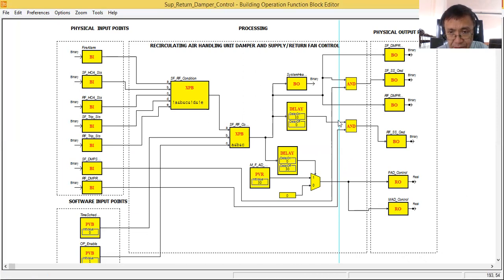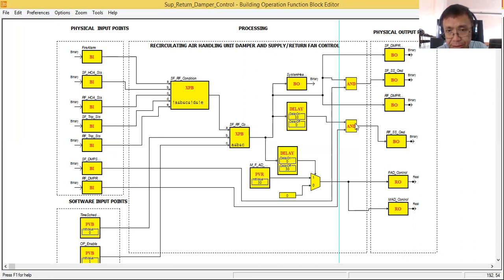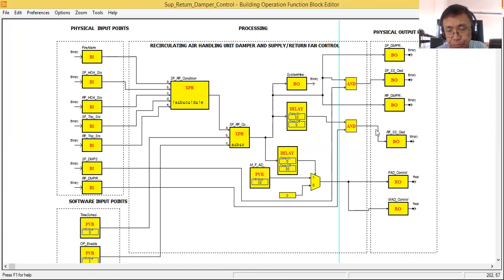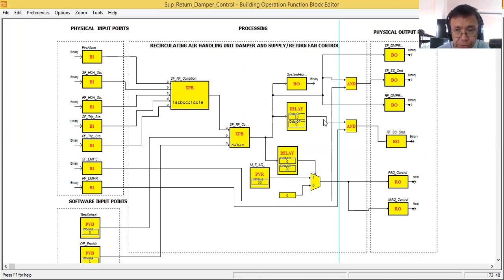Now I need to make some changes here. What I will do is move this delay after the output of this AND gate, so we will give a 10-second delay before the return fan starts. I can move this delay, remove it from here, then put it after the AND gate output. I'll show you that shortly.